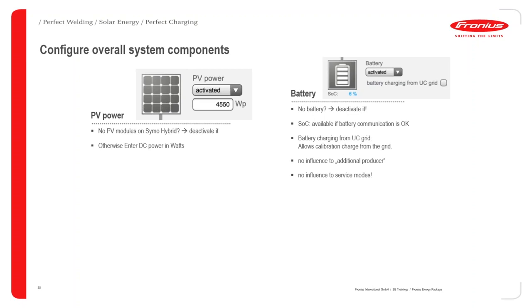So when you're doing all this, setting up the hybrid, one thing I forgot to mention at the start is you want to do this once everything's been connected. So you've got the inverter connected, the battery's been turned on and all wired up, and you've got the meter all turned on and wired up. So the whole system's been turned on, and then you want to go through with this commissioning here. So with the battery, you've then got the state of charge there, and if it's available, then it should come up with the actual state of charge. If the battery is not there, then you want to deactivate it.